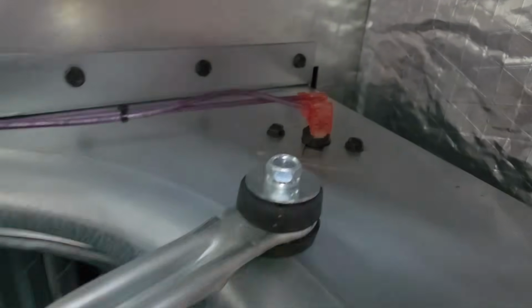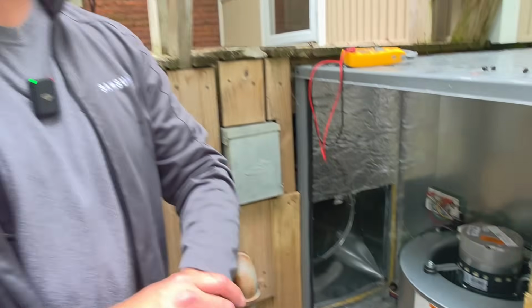I made sure that there was 24 volts across that switch, because if the limit switch opens, then that's an indication that there's a lot of heat, it's hot, and our blower is going to run. So I did check that as well. But this was just a mistake at the factory, a simple mistake, just landing a wire.